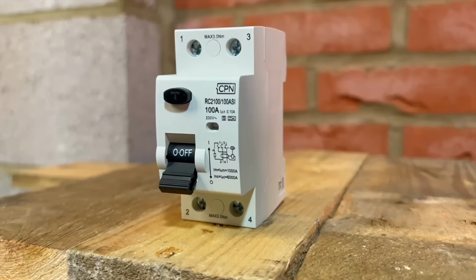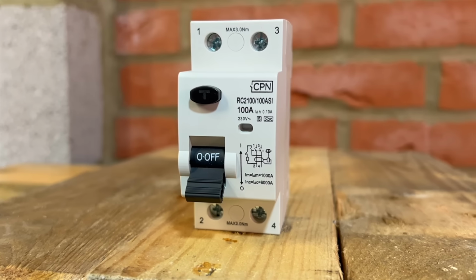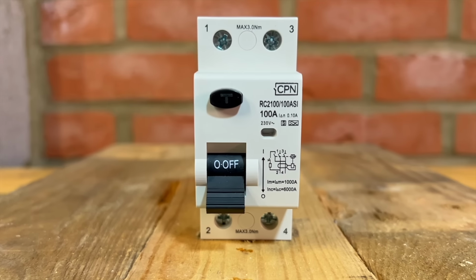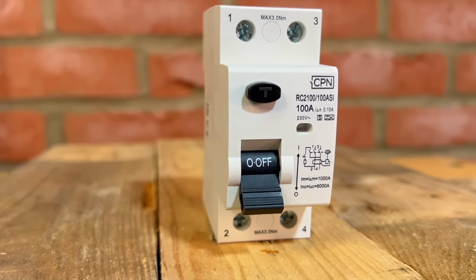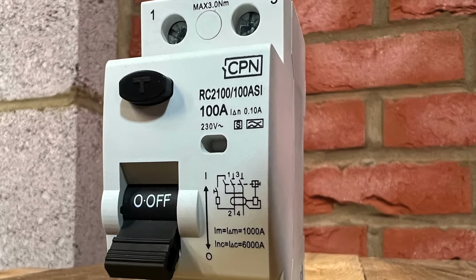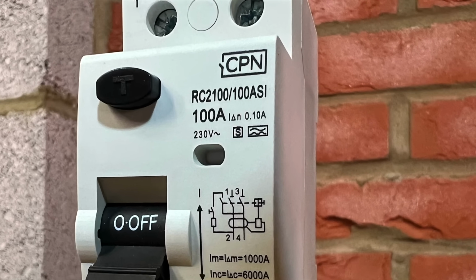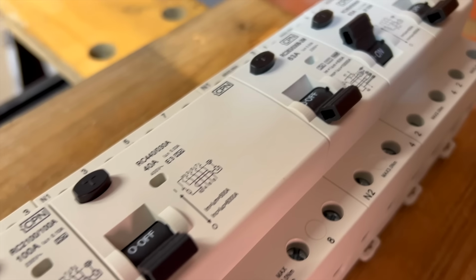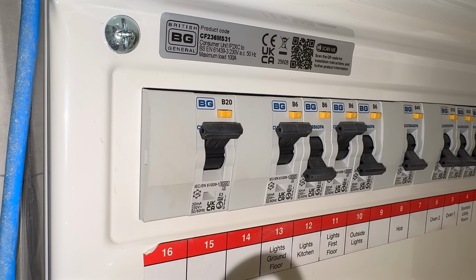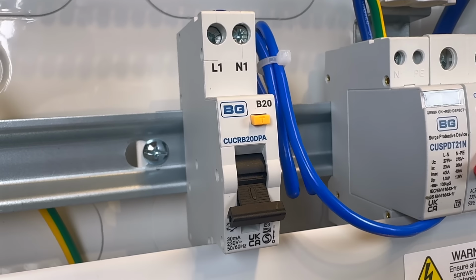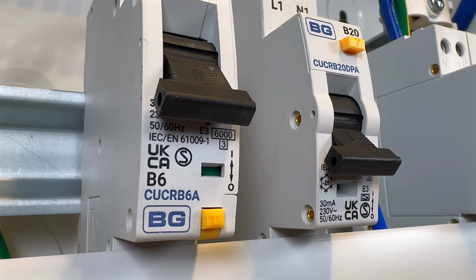In TT systems, this is usually an RCD. In many TT installations, a time-delayed Type S RCD is used for fault protection. This device is there to deal with earth faults and provide the disconnection required by BS7671. Downstream of that, we often use 30 mA RCDs or RCBOs. Those are not there for fault protection of the installation, they are there for additional protection.